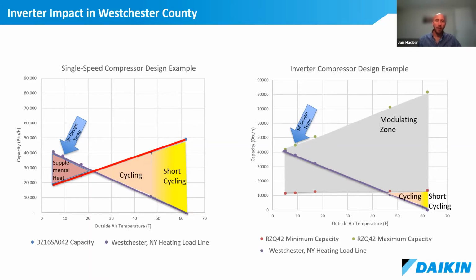On the left-hand side of this slide, there are a couple of important things to understand and consider. Firstly, when the capacity of the heat pump, which is shown in red, is higher than the load line, which is purple, that means that the heat pump can satisfy comfort and provide enough heat to keep the occupants comfortable. When that is reversed, when the red line is below the purple line, the heat pump cannot provide enough heat to maintain comfort and will need another source of heat. It could be electric resistance, it could be fossil fuel, but to maintain comfort, we're going to need to inject more heat. And because a single speed product is challenged to provide enough capacity when it's cold outside, in this example, we need supplemental heat.